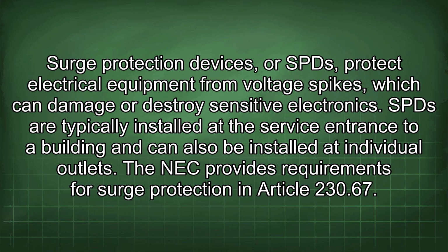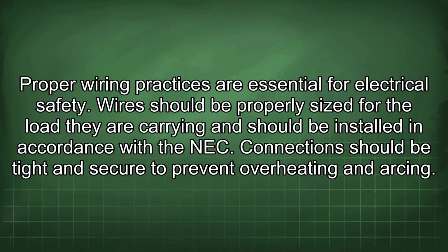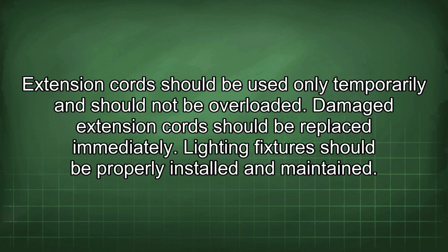The NEC provides requirements for surge protection in Article 230.67. Proper wiring practices are essential for electrical safety. Wires should be properly sized for the load they are carrying and should be installed in accordance with the NEC. Connections should be tight and secure to prevent overheating and arcing. Extension cords should be used only temporarily and should not be overloaded. Damaged extension cords should be replaced immediately.